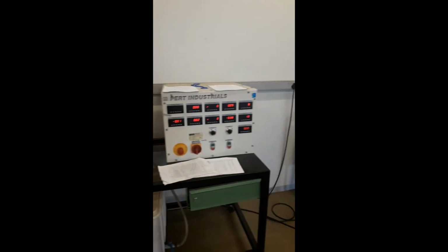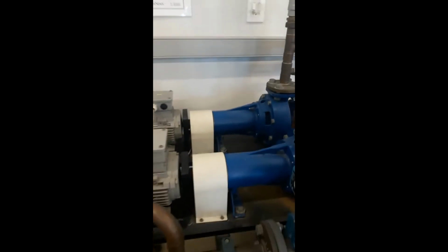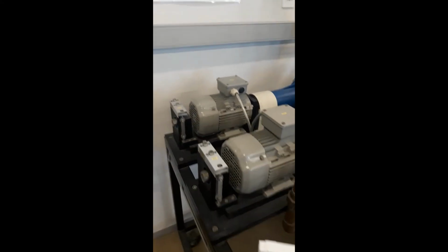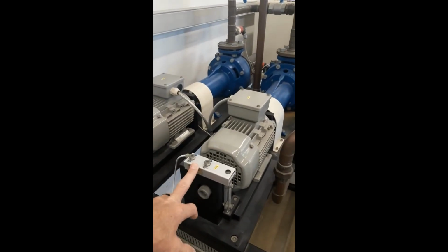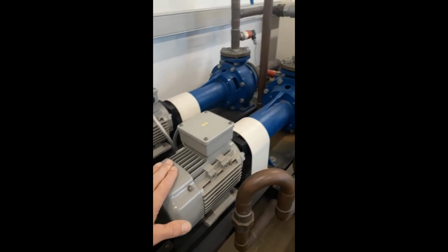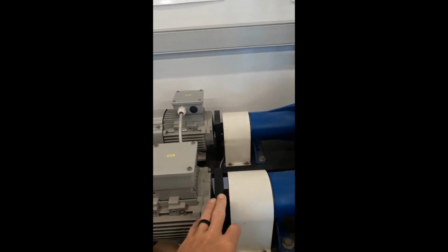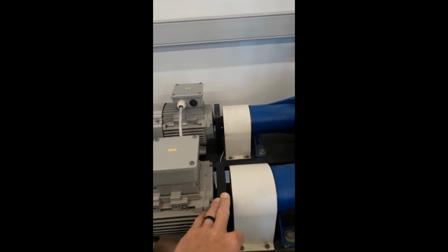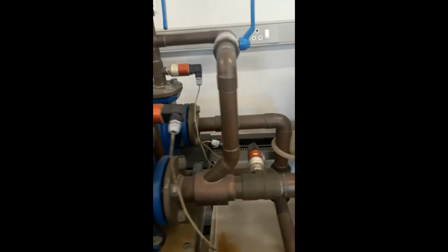The pump station we'll be using. So we have two pumps on the left and then the control panel for the two pumps. Let's start on this side. We have two pumps, pump number 1, pump number 2. Here at the back we have sensors. These are torque sensors. Then obviously the electrical motors that drive the pumps. We're going to measure the electrical inlet power. And then over here on the shafts, the speed, the RPM of the shaft, is measured. And again, pump 1, pump 2.